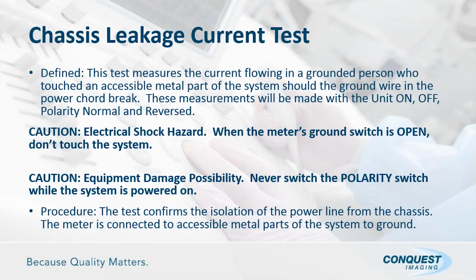There's a long time where people said you no longer need to concern yourself with reversed polarity versus normal, but NFPA has not removed that requirement, and so we need to make sure we're complying while we do this. Obviously, there's an electrical shock hazard. When you open the ground switch on the safety analyzer, basically, it's removing the safe path to ground, and now any other path it can find, it will use. So you create an unsafe or potentially unsafe condition when you open the ground switch.